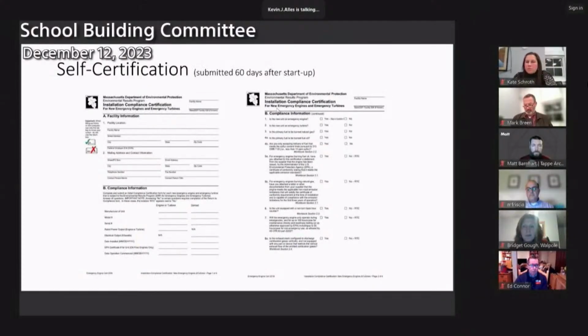This has been brought up in the past. The EPA has set guidelines for the generators, and part of those guidelines in terms of dealing with emissions is mandating the use of ultra-low sulfur fuels, that's 15 parts per million, which is the requirement for all Tier 2 generators going forward after 2006. So the EPA has set the guidelines, and the manufacturers are manufacturing these units to meet them. The manufacturers are not going to produce something and ship it out to a site that wouldn't meet the EPA guidelines.